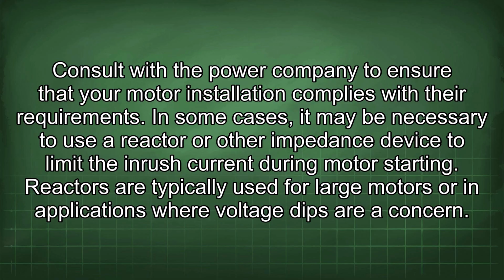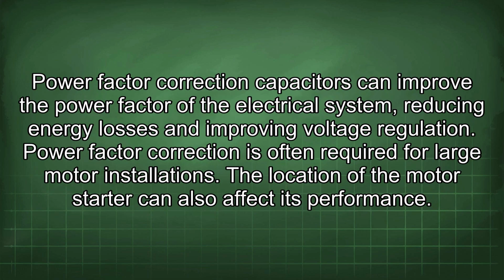In some cases, it may be necessary to use a reactor or other impedance device to limit the inrush current during motor starting. Reactors are typically used for large motors or in applications where voltage dips are concerned. Power factor correction capacitors can improve the power factor of the electrical system, reducing energy losses and improving voltage regulation. Power factor correction is often required for large motor installations.